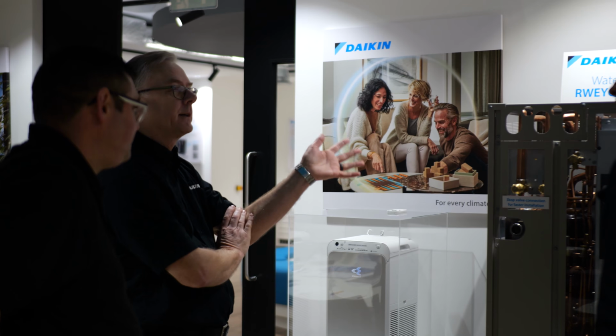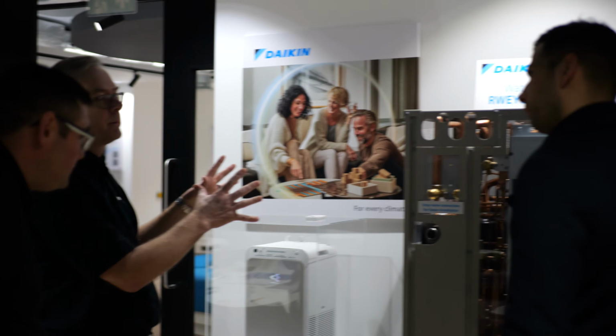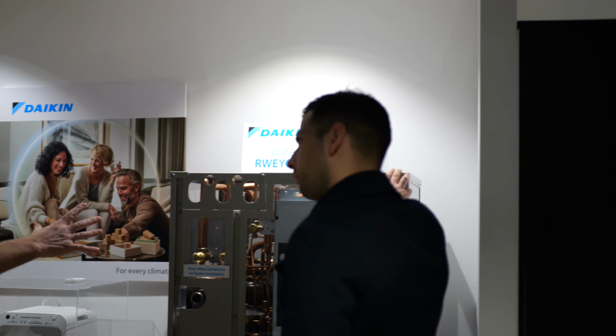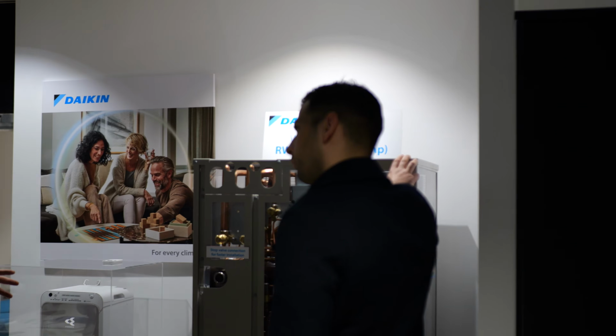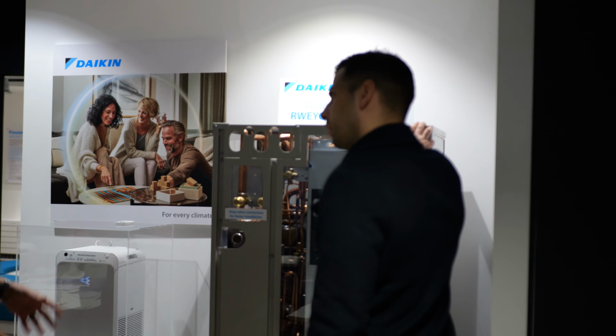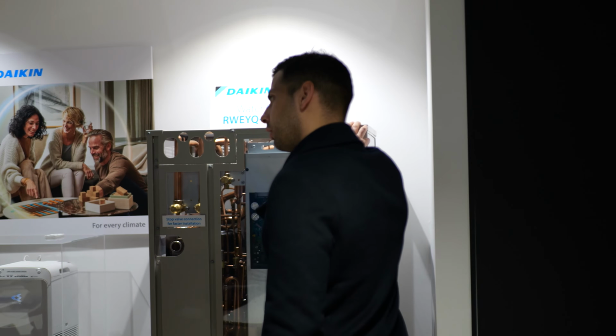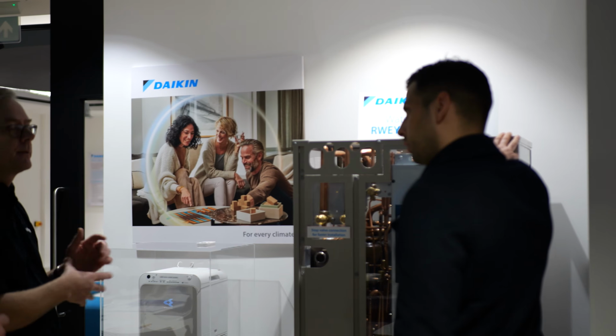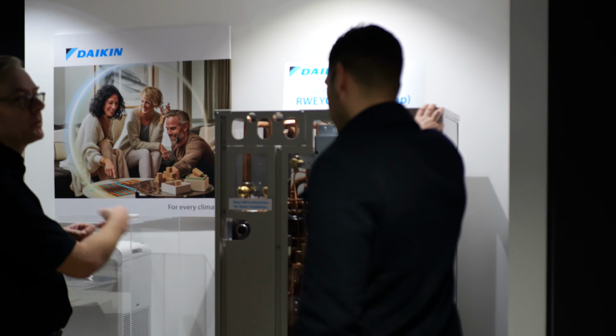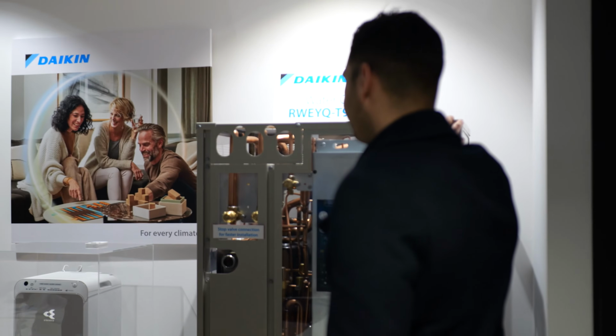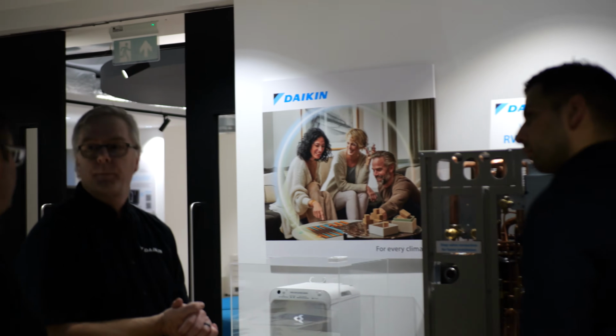Good application would be like a hotel. Hotels, yeah, small volume of refrigerant. You put this in the end of the corridor, do a VRV installation with your DX, and then you just do one water loop up to the roof, with a small chiller. So therefore it reduces the amount of refrigerant going into the hotel rooms. I see, it's also used as a full heat recovery system as well.